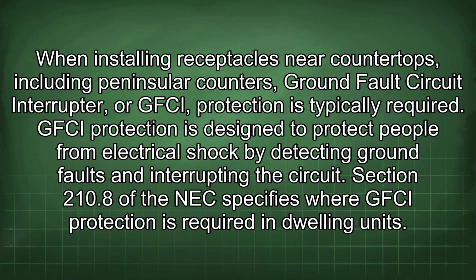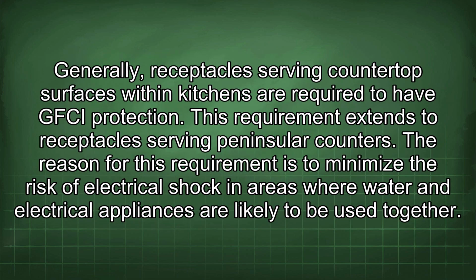Section 210.8 of the NEC specifies where GFCI protection is required in dwelling units. Generally, receptacles serving countertop surfaces within kitchens are required to have GFCI protection. This requirement extends to receptacles serving peninsular counters. The reason for this requirement is to minimize the risk of electrical shock in areas where water and electrical appliances are likely to be used together.